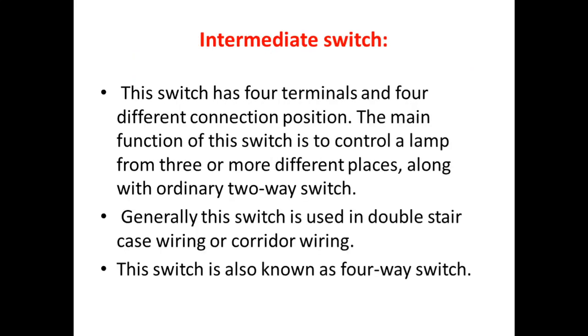Next is the intermediate switch. This switch has four terminals and four different connection positions. The main function of this switch is to control a lamp from three or more different places along with an ordinary two-way switch. Generally this switch is used in double staircase wiring or corridor wiring. This switch is also known as a four-way switch.